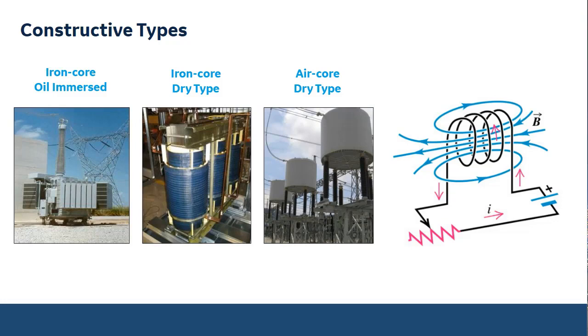Why does this solution have oil? The main thing is related to isolation: the oil in conjunction with the paper creates insulation between turns and also between the core and the base tank. And this is needed for very high, extra high voltage applications. So there is a special need for oil immersed, iron core type reactors.